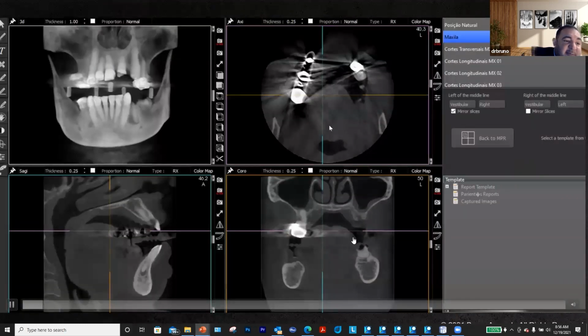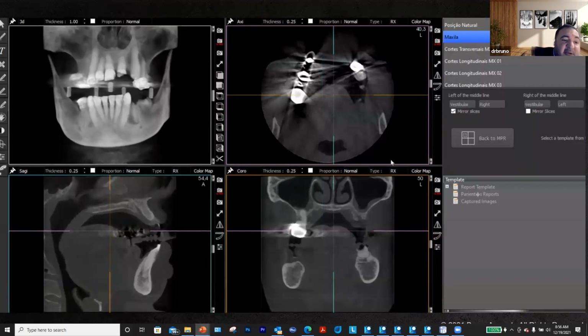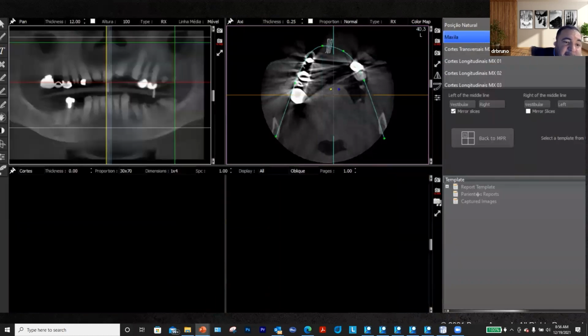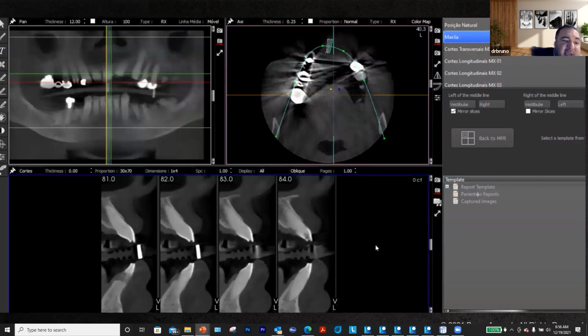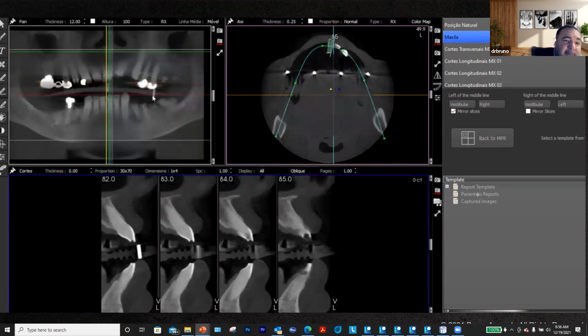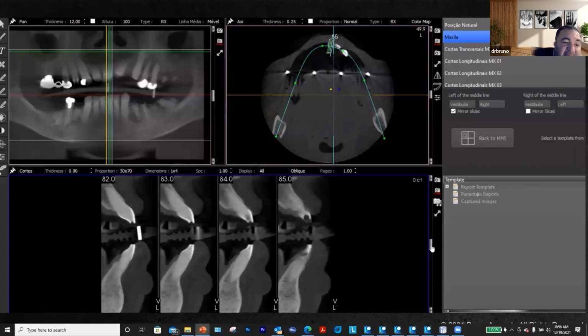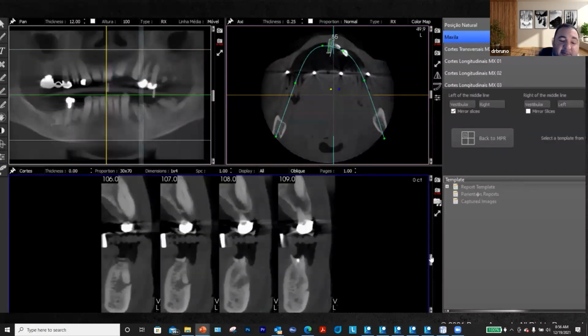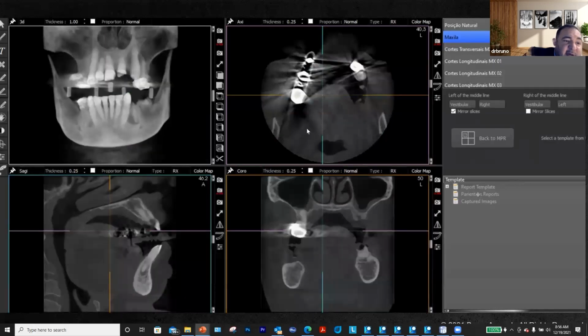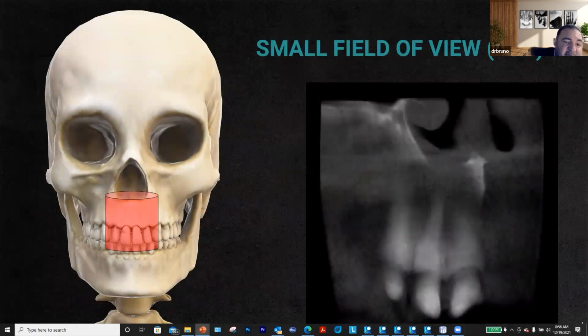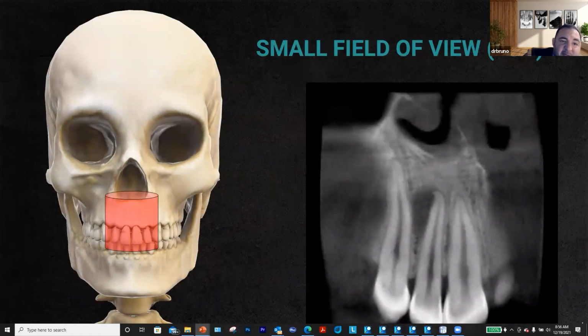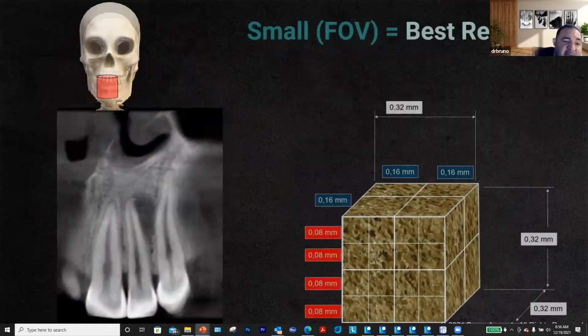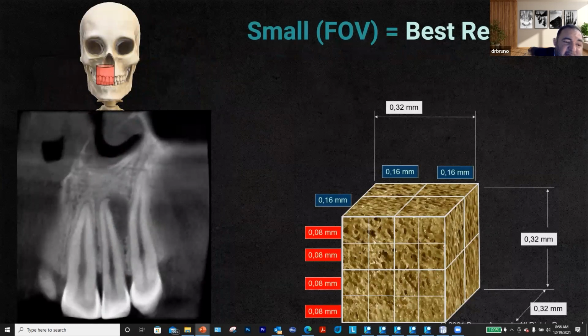This is actually a 10 by 10 from an Accuitomo, where I can start to get very good image quality, although I still have some scatter from some of the crowns. The overall resolution of the scan, to look for bone, detail of the anatomy and detail of the dentition, is pretty good. But in many ways, what we're looking for here is the showstopper, what Morita is known for: the ultra high resolution that we have with the smaller fields of view. In this particular case, we are using a very, very small voxel size of 0.08 to achieve the best resolution the unit can display.